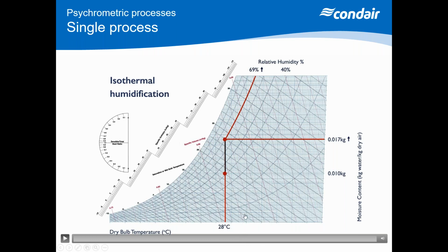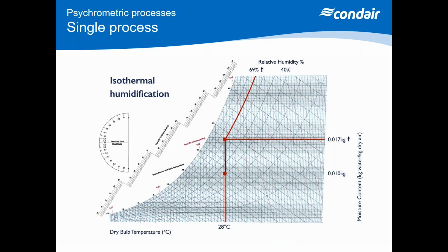But actually, it's not strictly true. You will see a slight increase in temperature from isothermal humidification, and it will come from two sources. You'll get a small bit of residual heat from the steam, but you'll also get some residual heat from the steam pipe. So the method of steam introduction is a stainless steel tube with holes in. It's got steam in. It's going to get hot, so there will be a radiant heat source in the airflow. Typically, you'll see 0.5 to 0.7 of a degree increase in temperature from isothermal humidification.